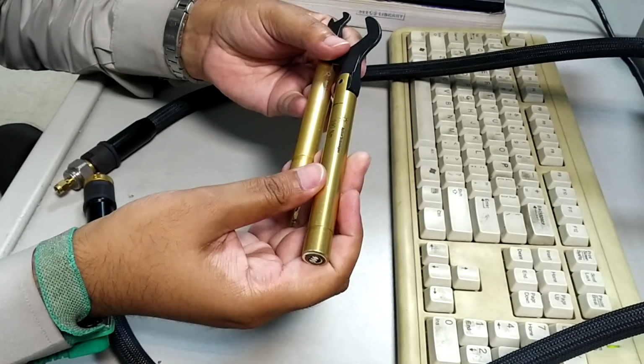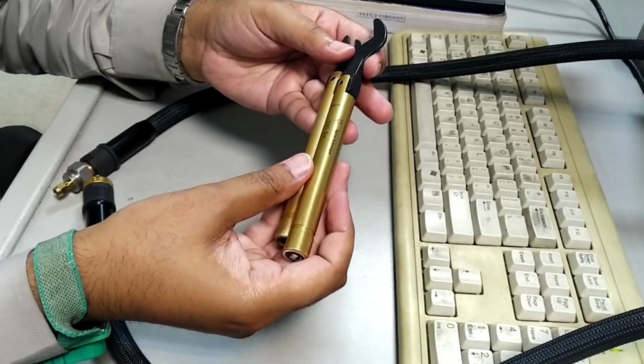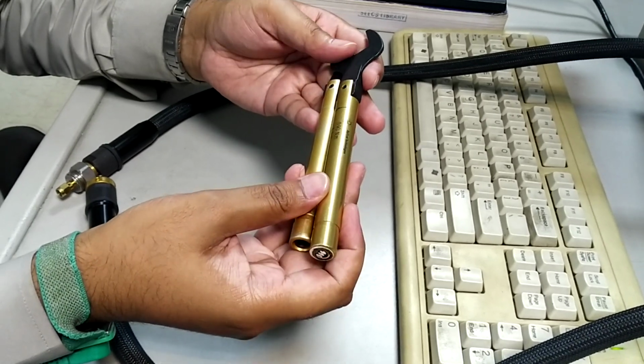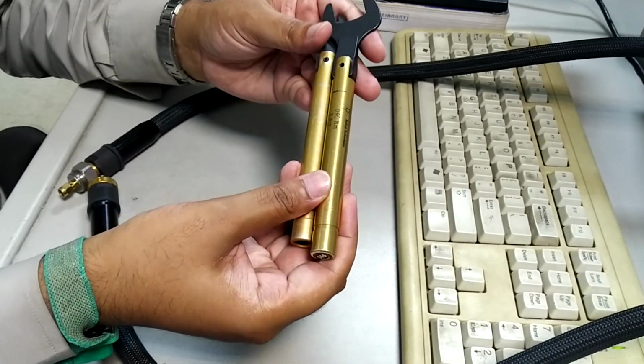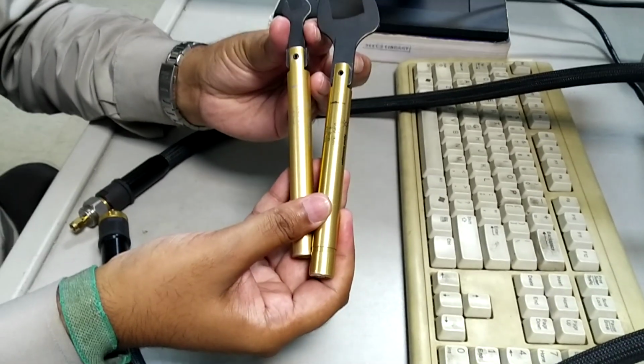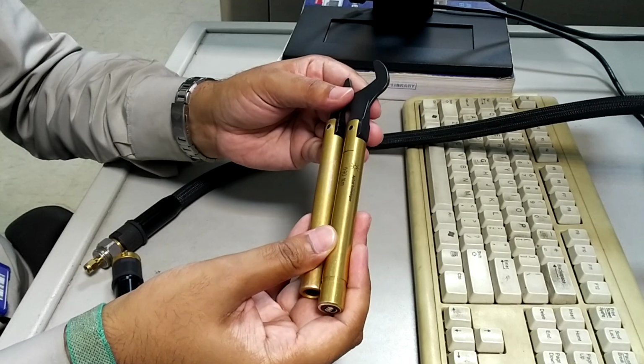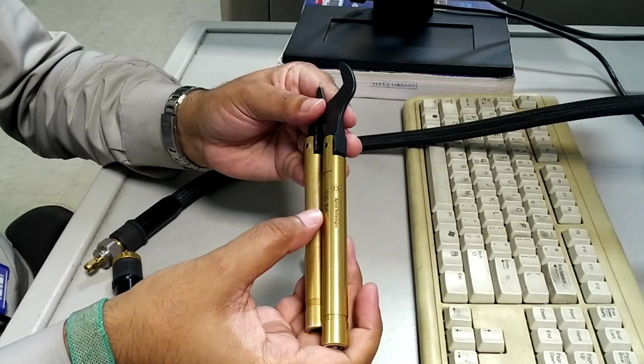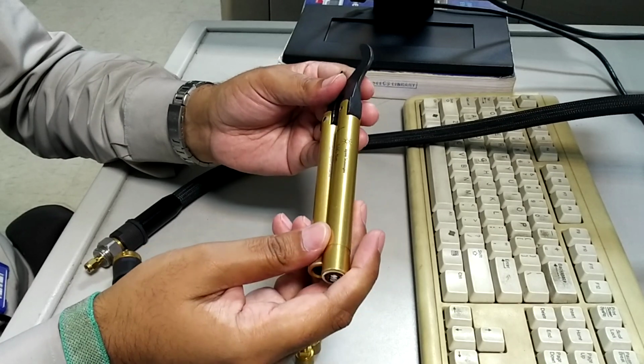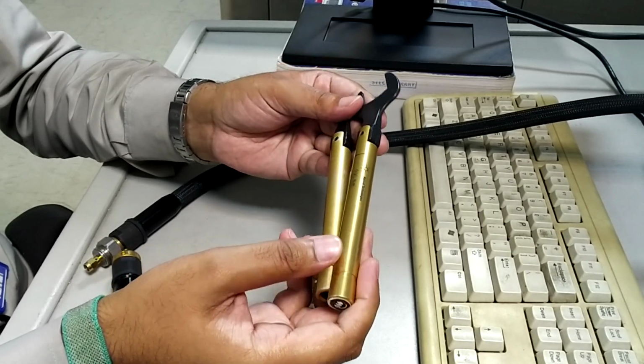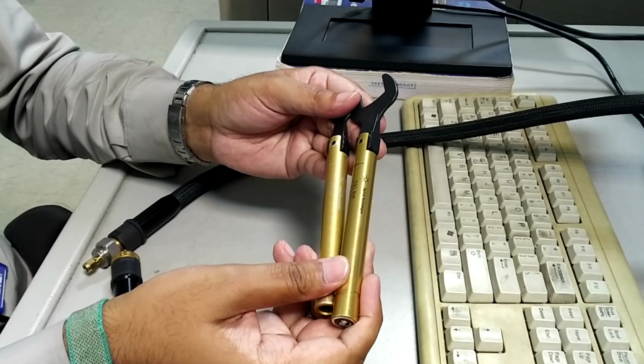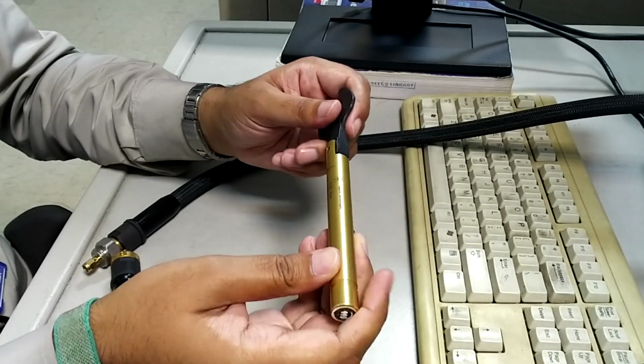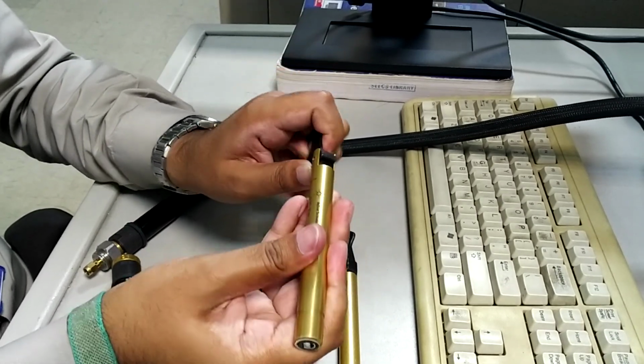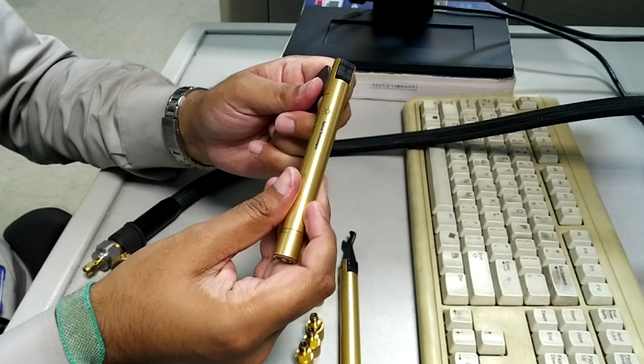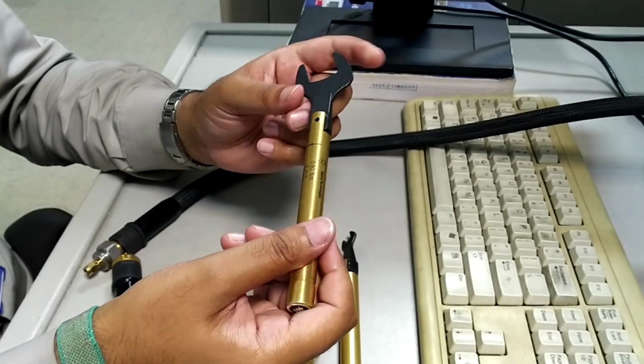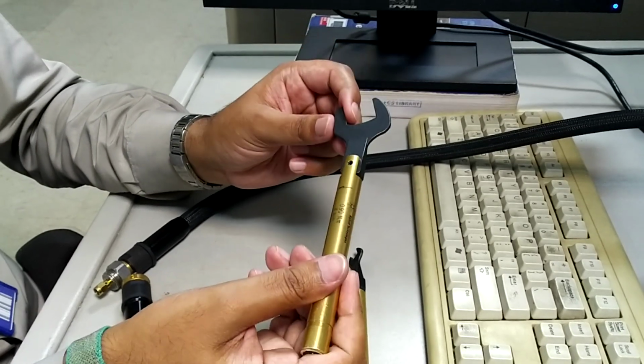Then this is important. There are two torque wrenches that are very important. As I told you in the class, don't connect the standard with force. If you connect the standard with force, you can damage it very easily. So there are two torque wrenches available in the calibration kit, one with a small size and one with a large size, and both have a recommended torque of 0.90 Newton meter. So this is the standard torque that you can apply to connect our calibration standard. You can't use more force in that case. If you use this torque wrench and apply too much force, it just bends. As you can see here, it doesn't allow you to put too much force on the calibration standard. So this makes the calibration standard safer.